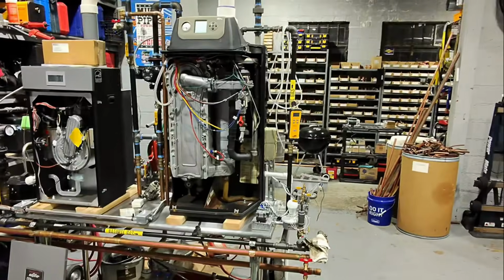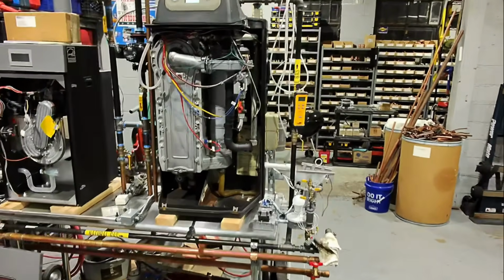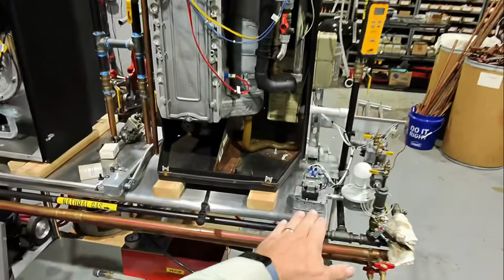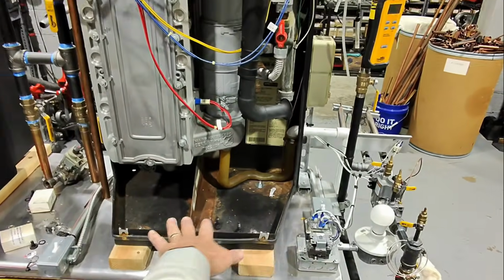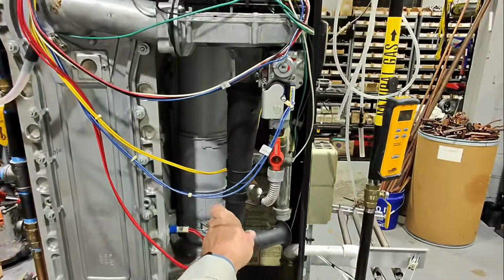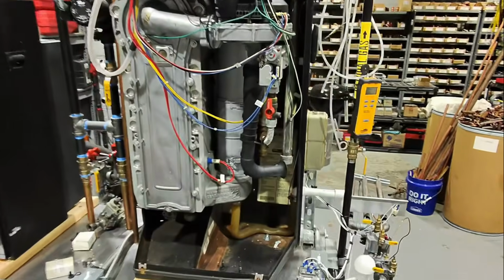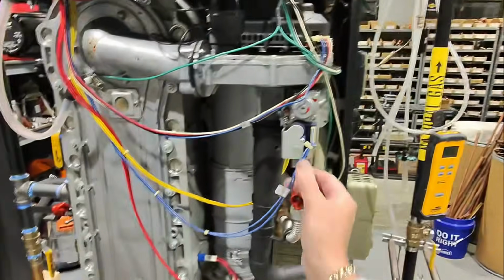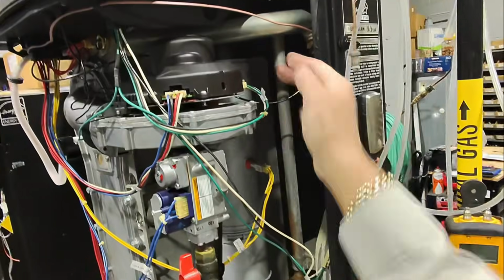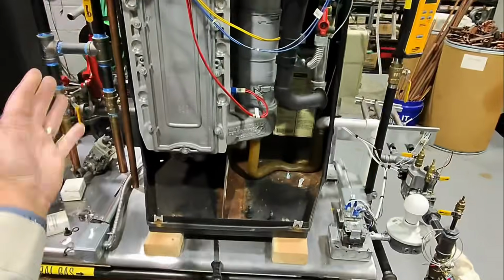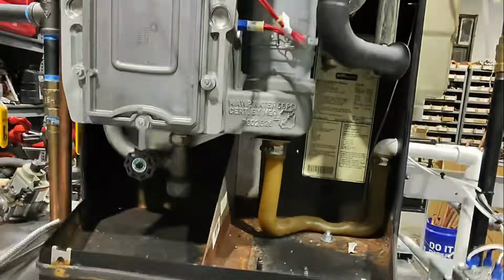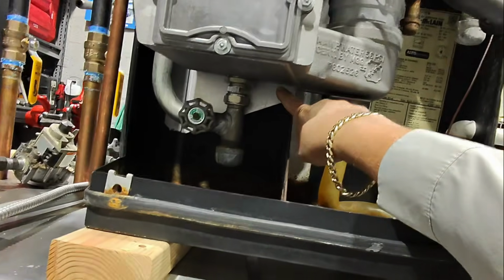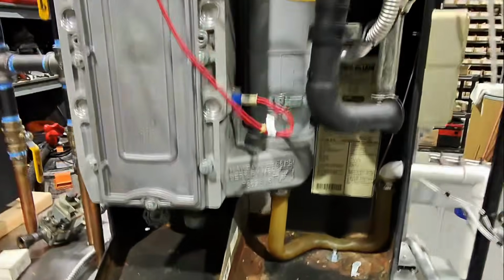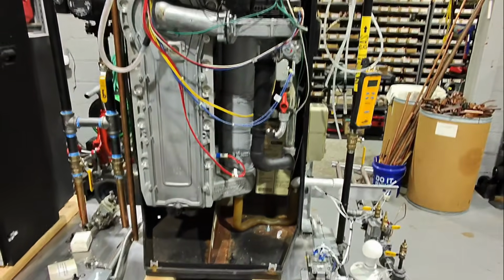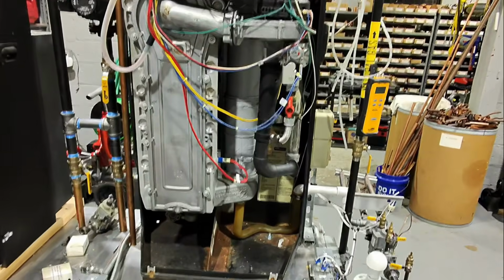First, we're going to do a visual inspection to make sure there's nothing out of the ordinary going on. Make sure there's no water resting at the bottom of the unit, making sure that our silencer is connected, making sure all of our wiring is connected. Nothing out of the ordinary. We're going to do a quick little visual inspection of the bottom of the heat exchanger. They are known to develop a hole at the bottom, which would result in a heat exchanger replacement at a minimum, which is typically caused by improper maintenance.